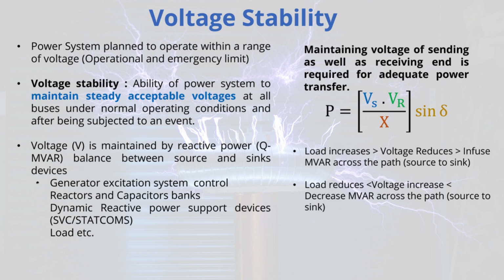The material lists sources and sinks. Sources include generator excitation systems, they're adjustable MVAR sources. Capacitor banks explicitly provide MVARs. And dynamic devices like SVCs and STATCOMs can inject or absorb MVARs very quickly. Sinks are mainly inductive loads, like motors, and also transmission lines themselves consume reactive power when heavily loaded.